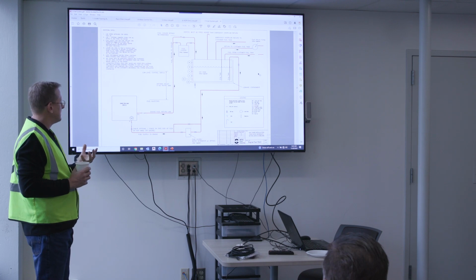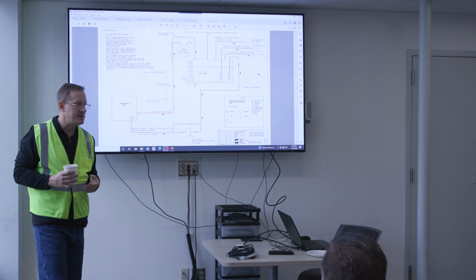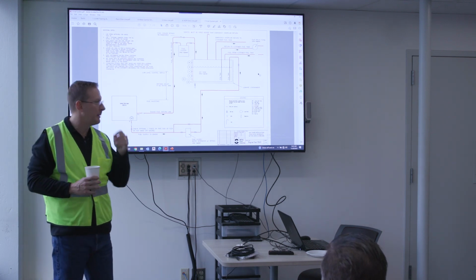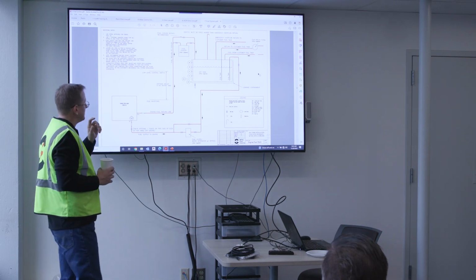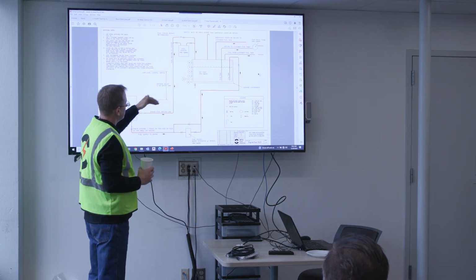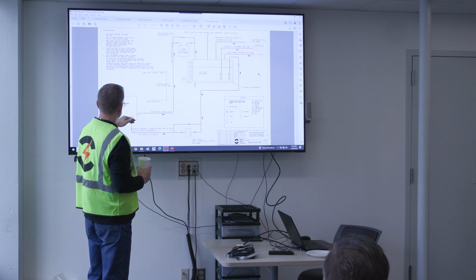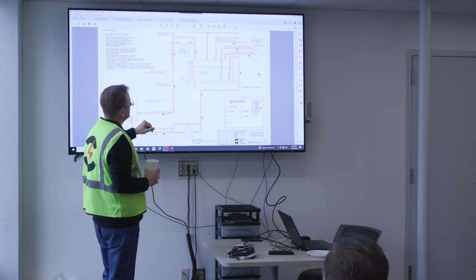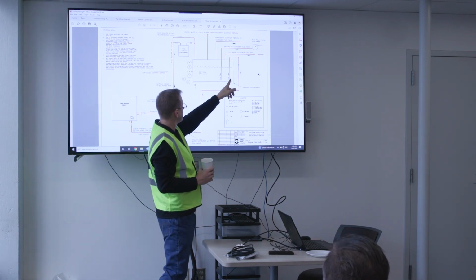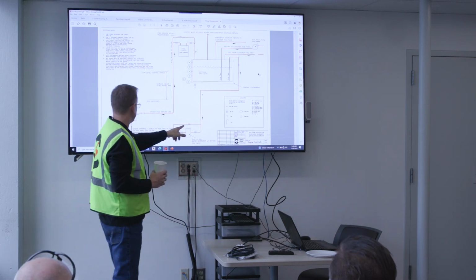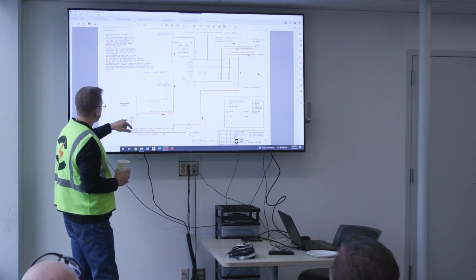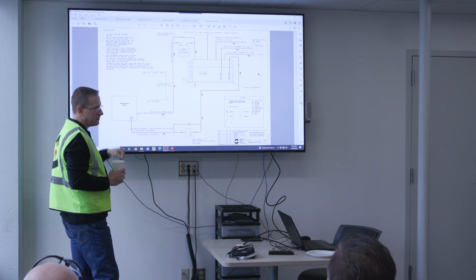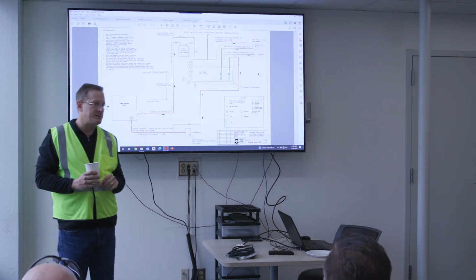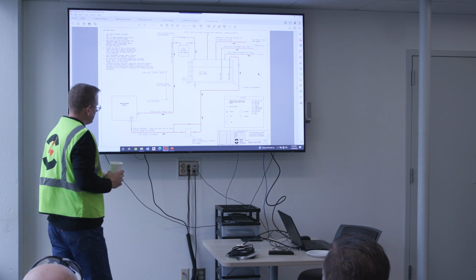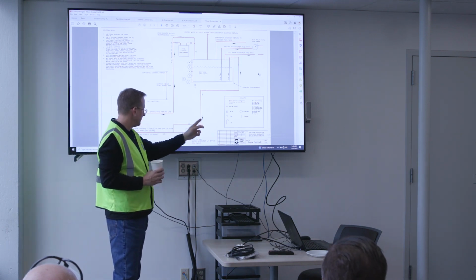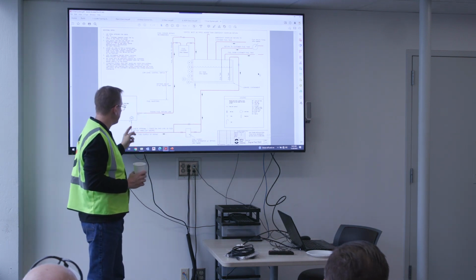And this is another method that we use to ensure a start of the diesel, because we want to make sure that we don't lose prime. So there's always some fuel pressure because of the raised tank coming into the engine. So we've got basically a feed from the day tank through a drop tube coming out and providing gravity feed into the engine itself. So there's always fuel here. It's always ready to go. It's not going to lose prime. We do run it through a fuel filter water separator on the way to the engine.